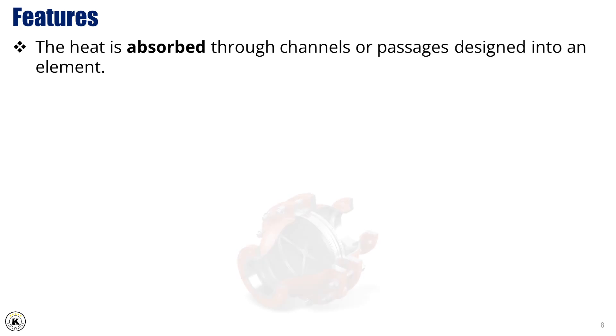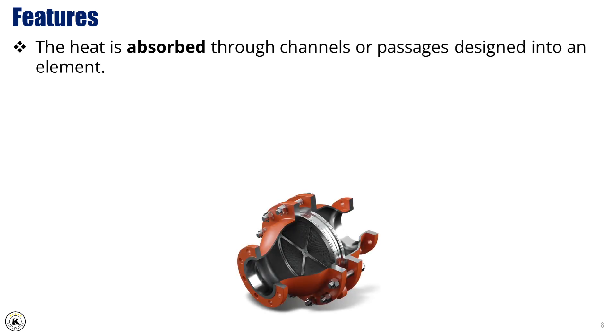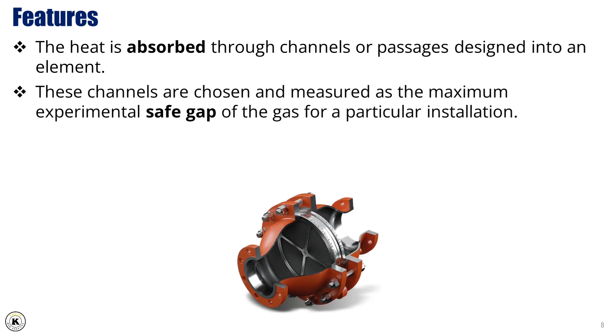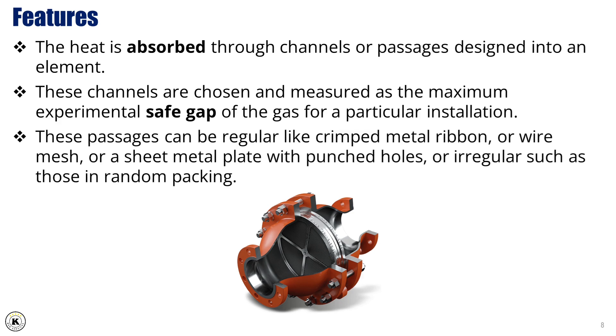The heat is absorbed through channels or passages designed into an element. These channels are chosen and measured as the maximum experimental safe gap of the gas for a particular installation. These passages can be regular, like crimped metal ribbon, wire mesh, or a sheet metal plate with punched holes, or irregular, such as those in random packing.